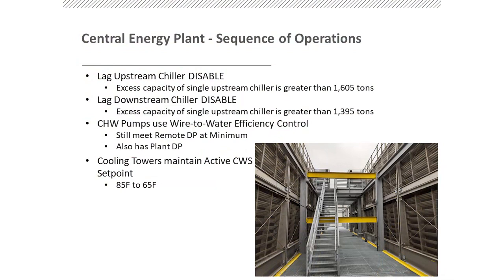So that's how you turn on your chiller. Fortunately for us, the good engineer didn't write the reverse sequence to turn off your chillers, because we all know that's not possible. And so up here is how you're going to disable these. When your lag upstream chiller is running, you're going to disable it. It's essentially looking at the excess capacity that you have in the plant and determining whether you need that whole chiller or not. It'll turn off your upstream chiller, and then do the same thing for the downstream chiller, in essence, until you get to the minimum number of chillers running.